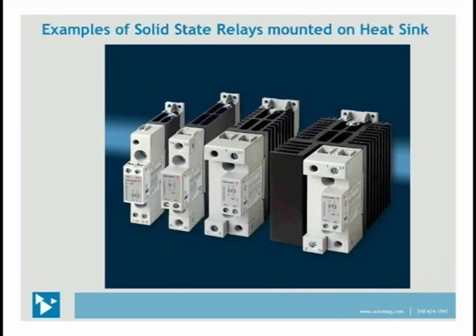Here are some of the drawbacks of a solid-state relay. When closed, the solid-state relay has a higher resistance than an electromechanical relay and will generate heat and electrical noise. When open, the solid-state relay has lower resistance, which develops reverse leakage current, typically in the microamps range. Now, an electromechanical relay has a lower ohmic resistance. When the mechanical switch is closed, it has very low resistance, and a very high resistance when the contacts are open because of the air gap between them.